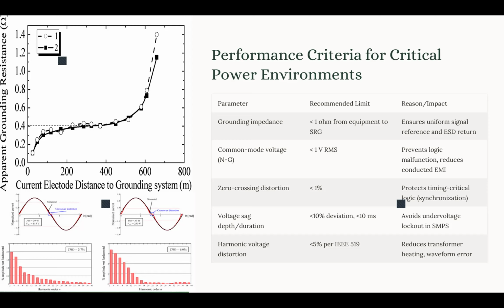We said some of the disturbances in the power supply are, for example, voltage sag or so. It could be a drop of voltage amplitude or an increase in voltage amplitude. Now, the voltage sag, for example, has two parameters that define the intensity of the voltage sag. One is the depth of the voltage sag, meaning the amount of dropped voltage. So we have a nominal voltage that the voltage should be. And when we have a voltage sag, that means the voltage dropped to another, undesired level. The difference between the desired level and the real, undesired level of the voltage sag is the depth of the voltage sag.